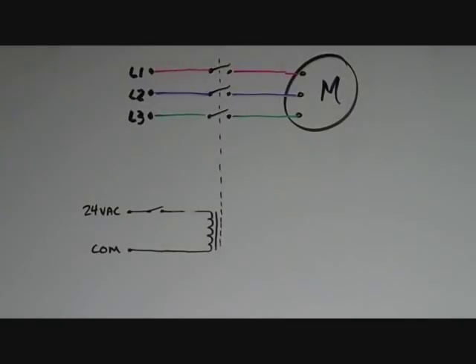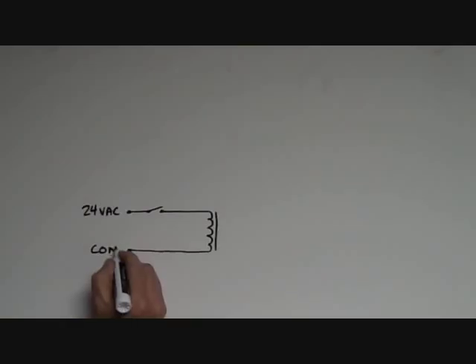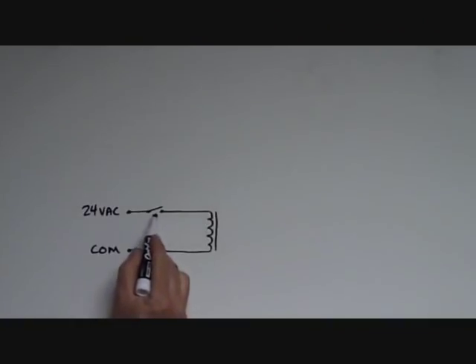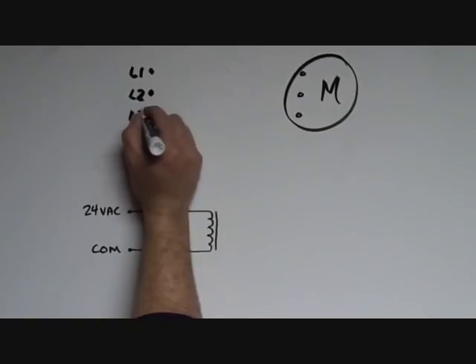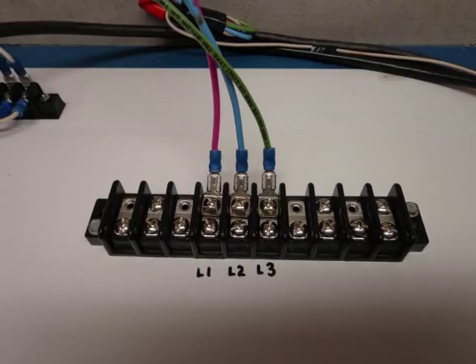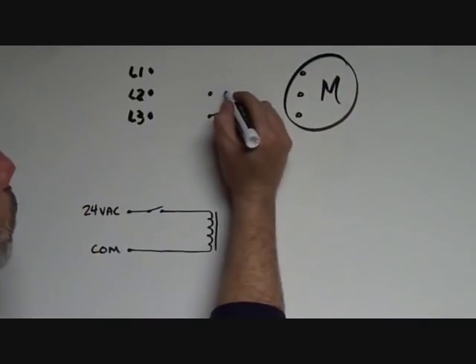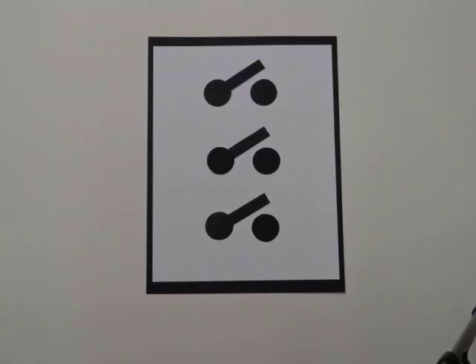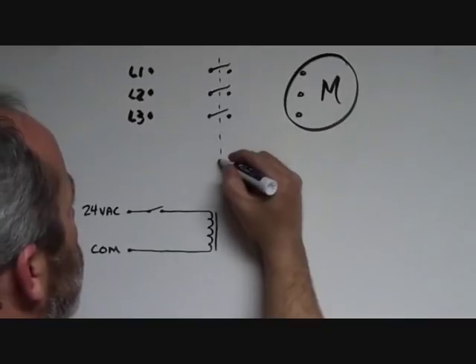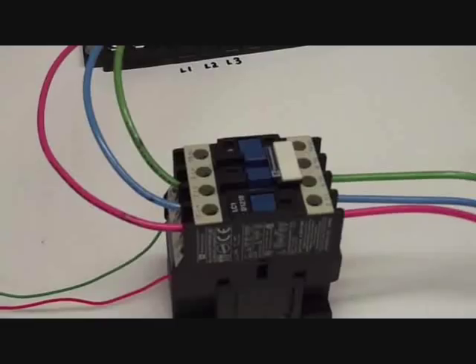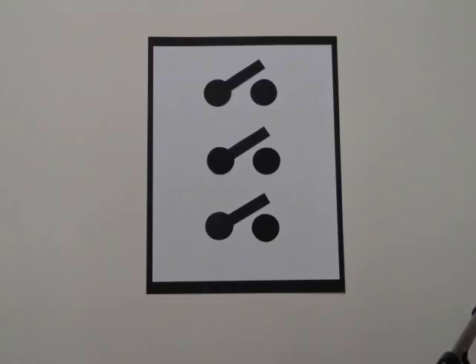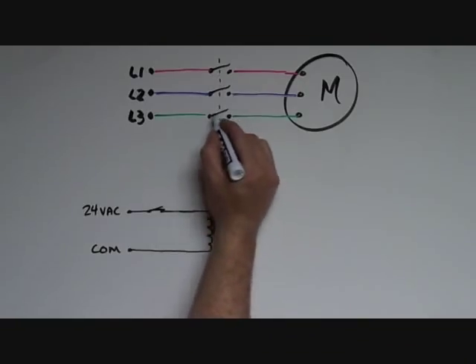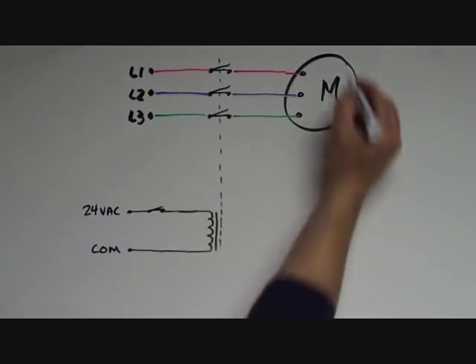Here's the schematic for what we've done so far. We have the 24 volt coil with terminals A1 and A2. We have our 24 volt power supply and a switch to make or break the power to the coil. This is our constant 460 volts from the building power in three phases. This is the motor with its three terminals, and these are the three poles of the contactor that will open and close together when the coil is energized. This dashed line represents the magnetic force from the coil that pulls the contacts closed. So when I energize the coil by pressing the push button, it closes the main contacts and connects lines 1, 2, and 3 to the motor's three windings labeled 1, 2, and 3 respectively.